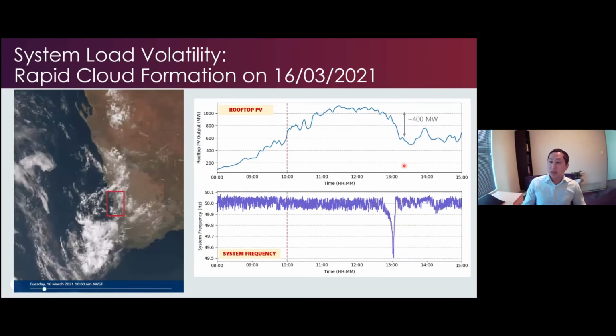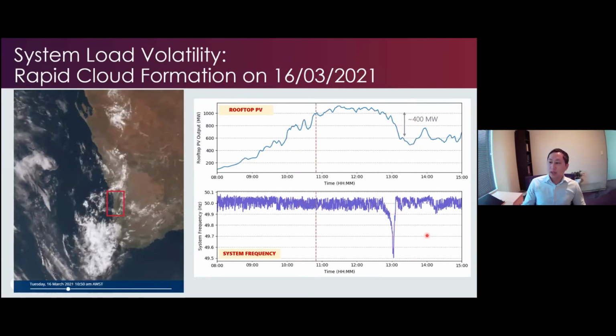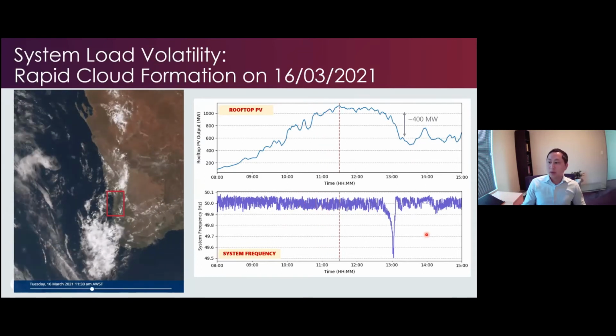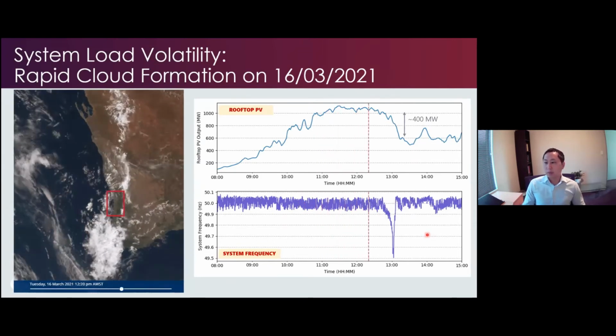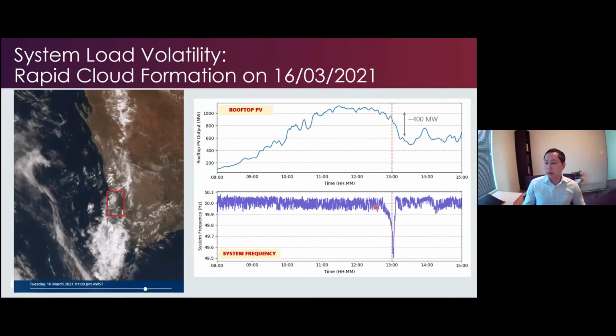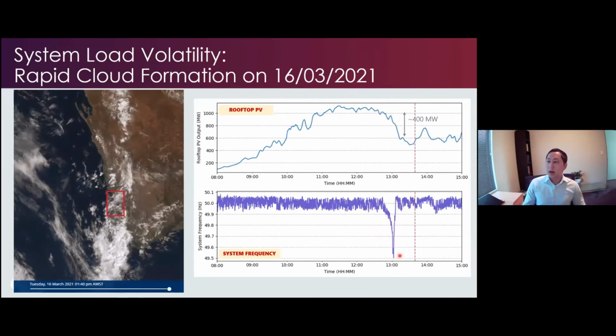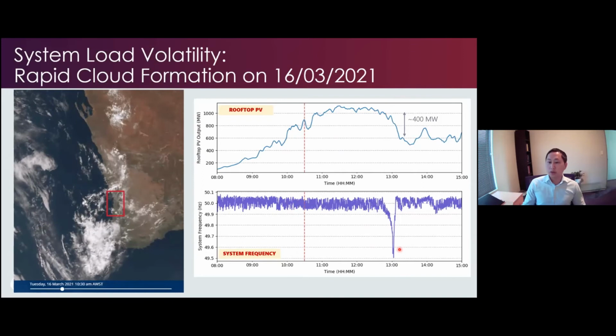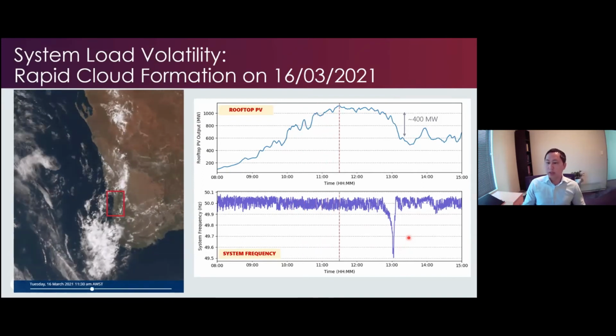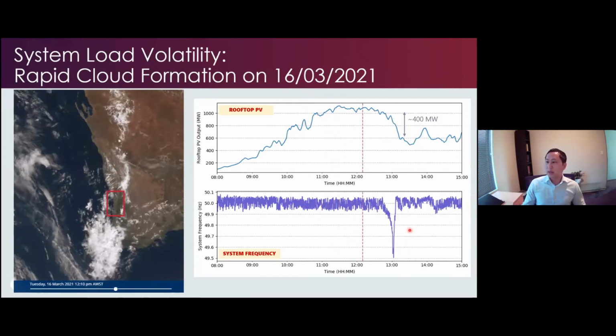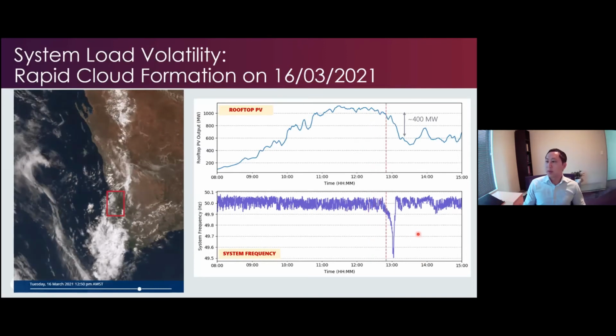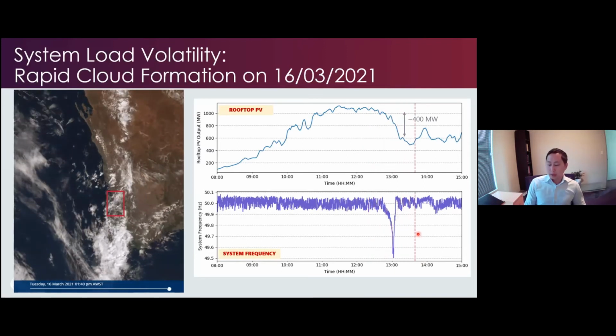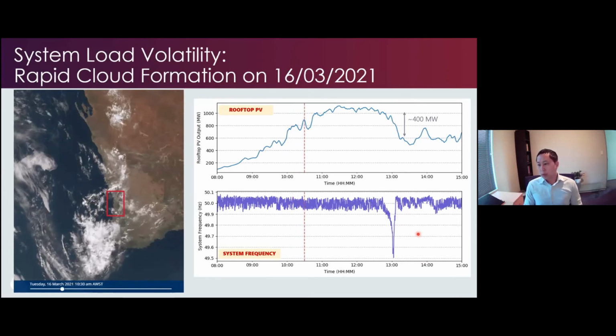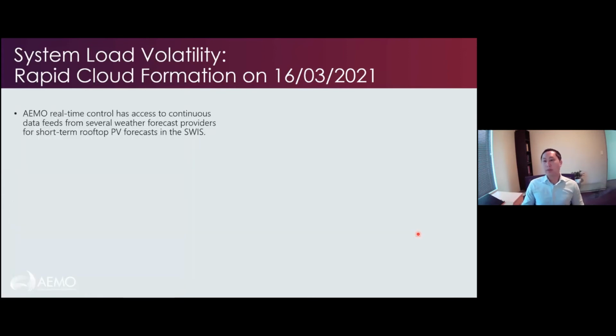That actually looked a lot like a generator contingency. So we were not prepared for it in terms of real-time control, and the frequency went down to 49.5 hertz. We actually had to use spinning reserve, or FCAS contingency raise, to bring the frequency back up. And one of the questions people are asking is, what happened to the forecasts?